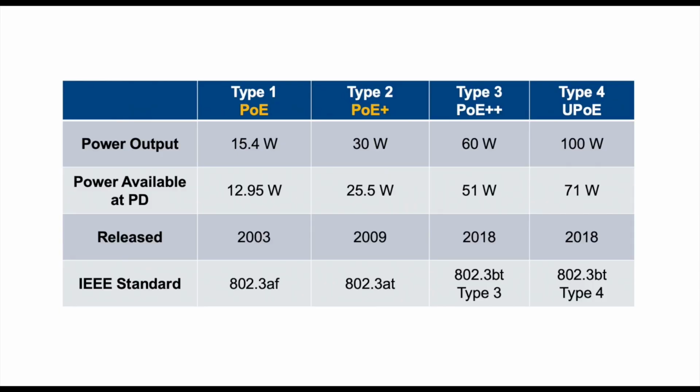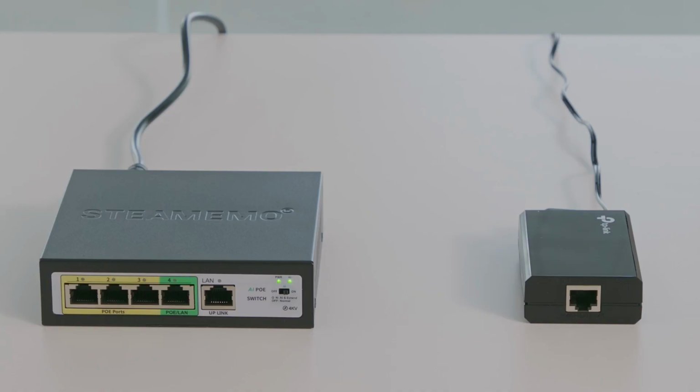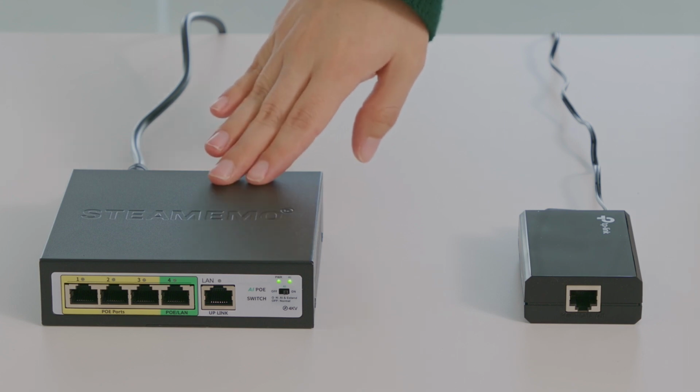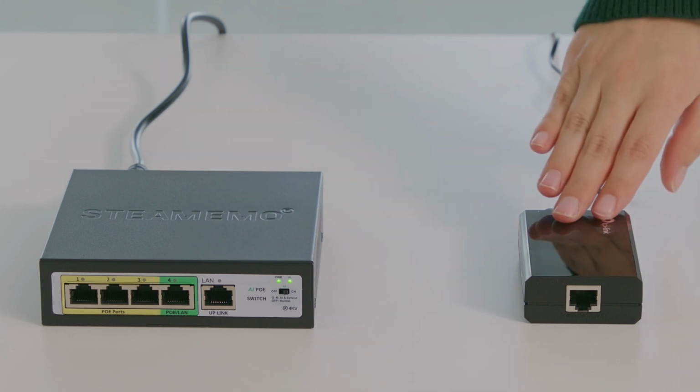The 1600 transmitter is compatible with Type 1 or standard PoE and Type 2 or PoE Plus devices. Type 1 PSEs have 15 watts available at each Ethernet port, while Type 2 have 30 watts available. The 1600 will only consume up to 11 watts, making PoE an option that reduces wiring without sacrificing functionality. The two PSE examples we will review today are a PoE Network Switch as well as a PoE Injector.